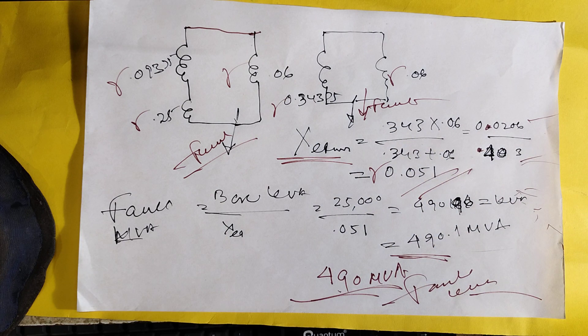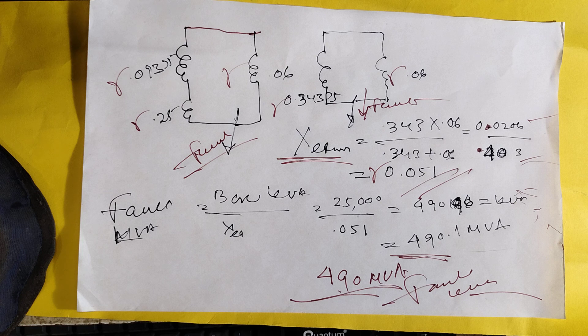The equivalent reactance is coming 0.051 per unit. Your base KVA, fault KVA is the base KVA divided by per unit X, equivalent reactance. So 25,000 KVA divided by 0.051 is equal to 490 MVA. So your fault MVA is 490 MVA.